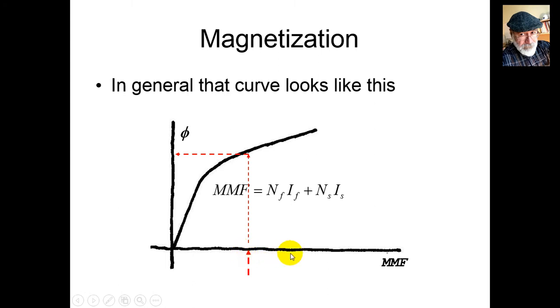The manufacturer decided to divide that value by NF and present the horizontal axis as IF*, IF asterisk. That's the value on the horizontal axis - the equivalent field coil current that would create the same total magnetomotive force as both coils combined.